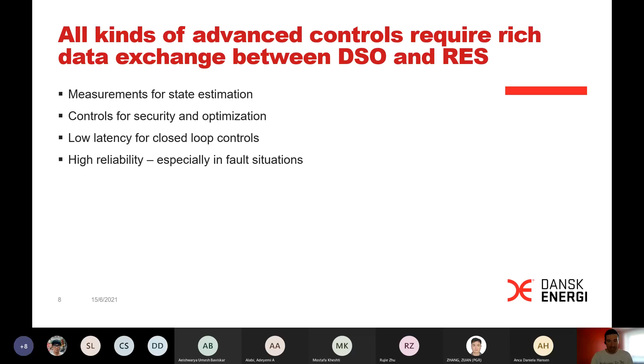What we're seeing in Denmark now for distributed energy resources—here I've illustrated with a wind turbine, but it's actually more commonly combined heat and power plants, the smaller local combined heat and power plants—is that there is a need for more measurements, not only the current coming out of this device, but what about the state of a breaker? Is a synchronous generator synchronized or not? You can't necessarily know that only by taking measurements in the station.